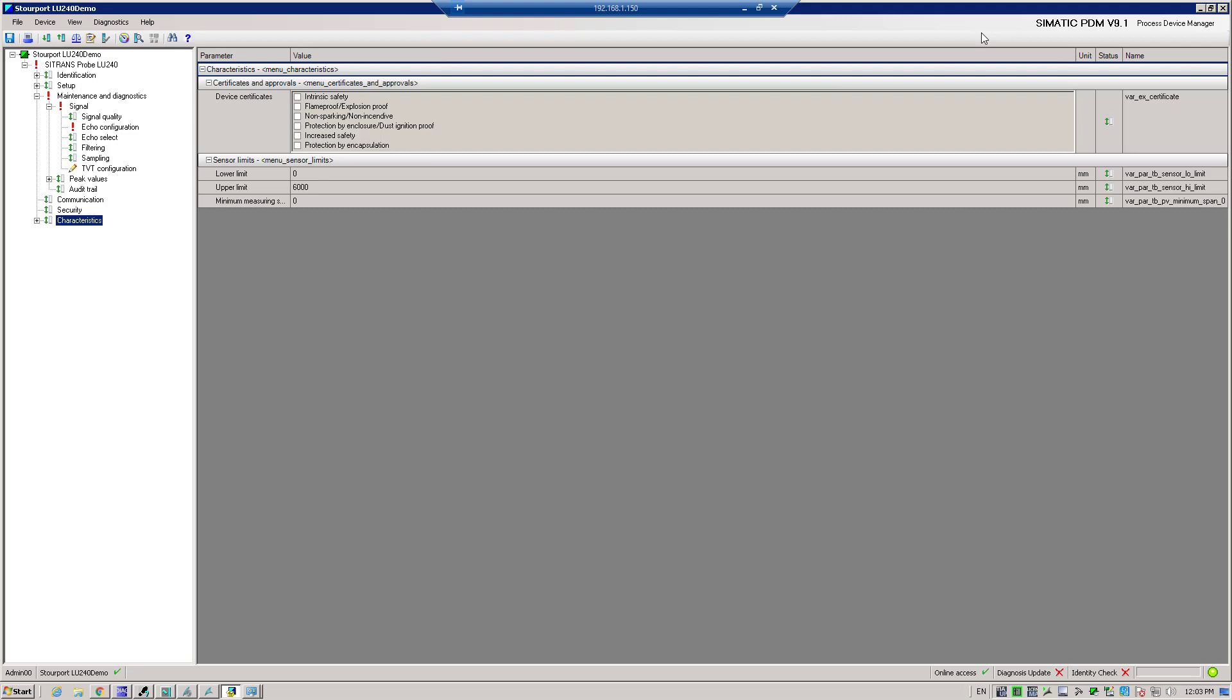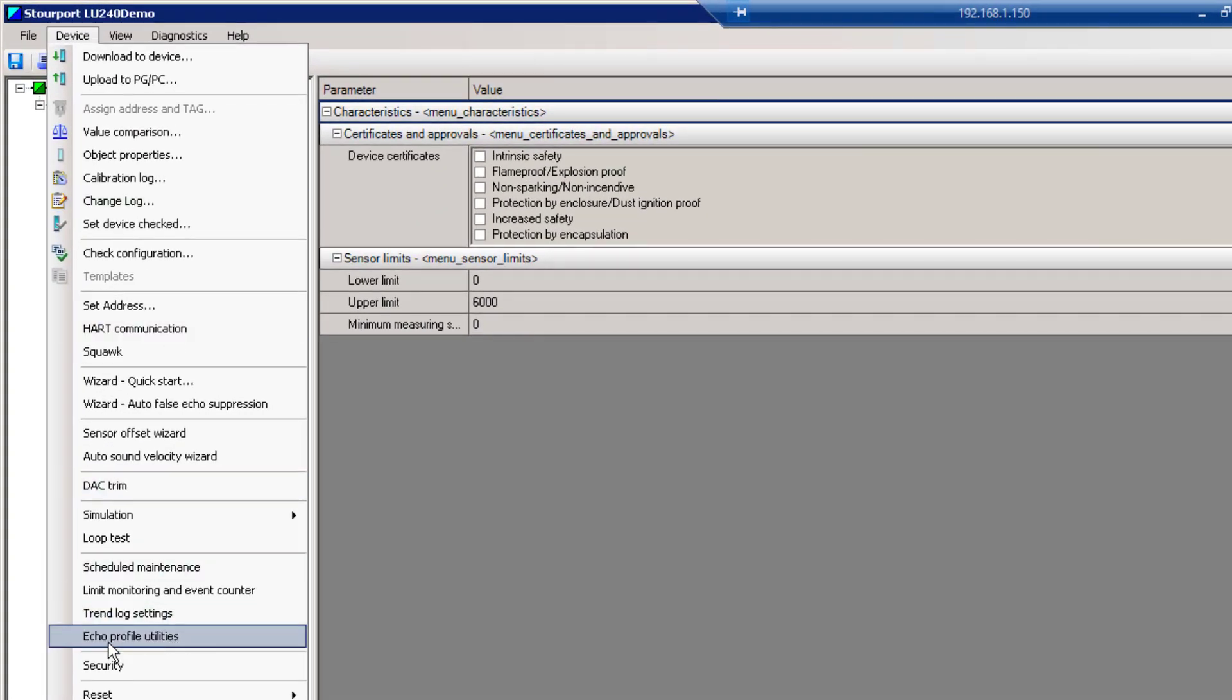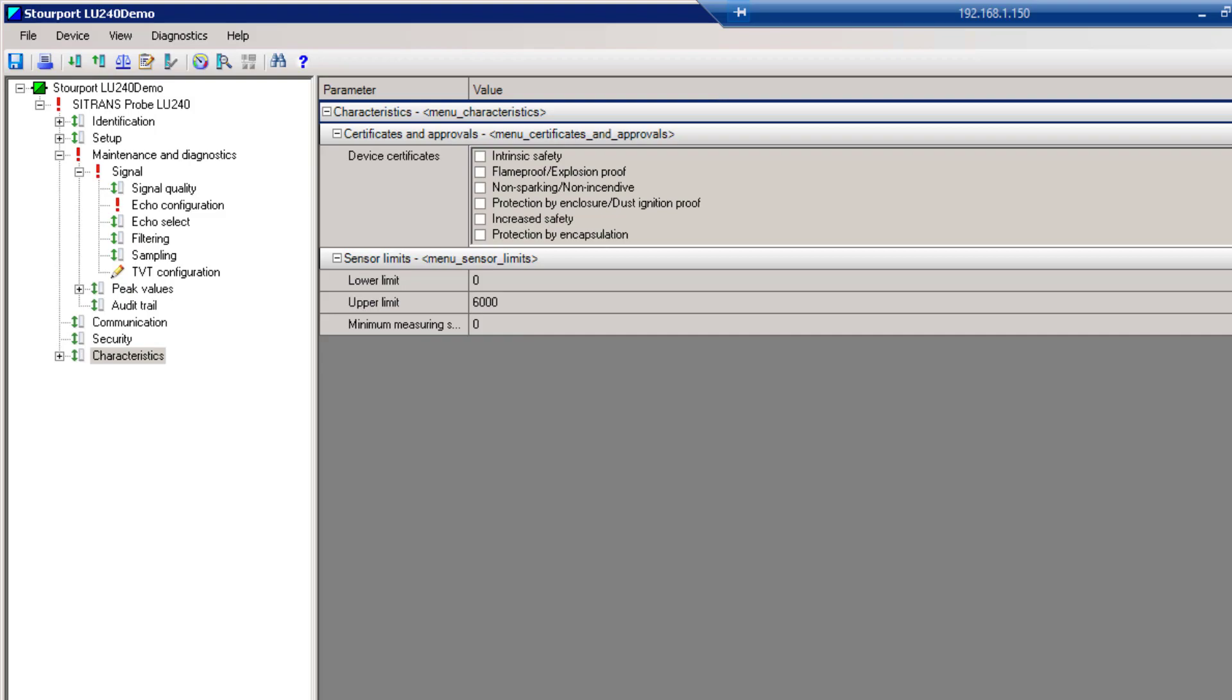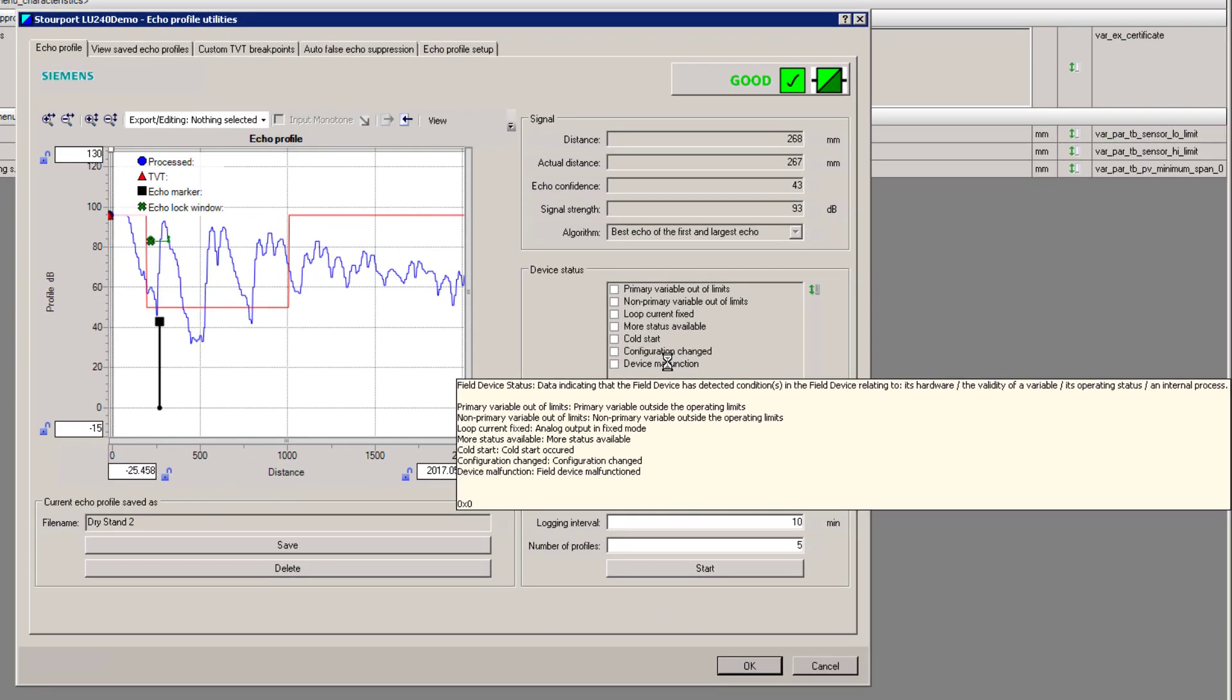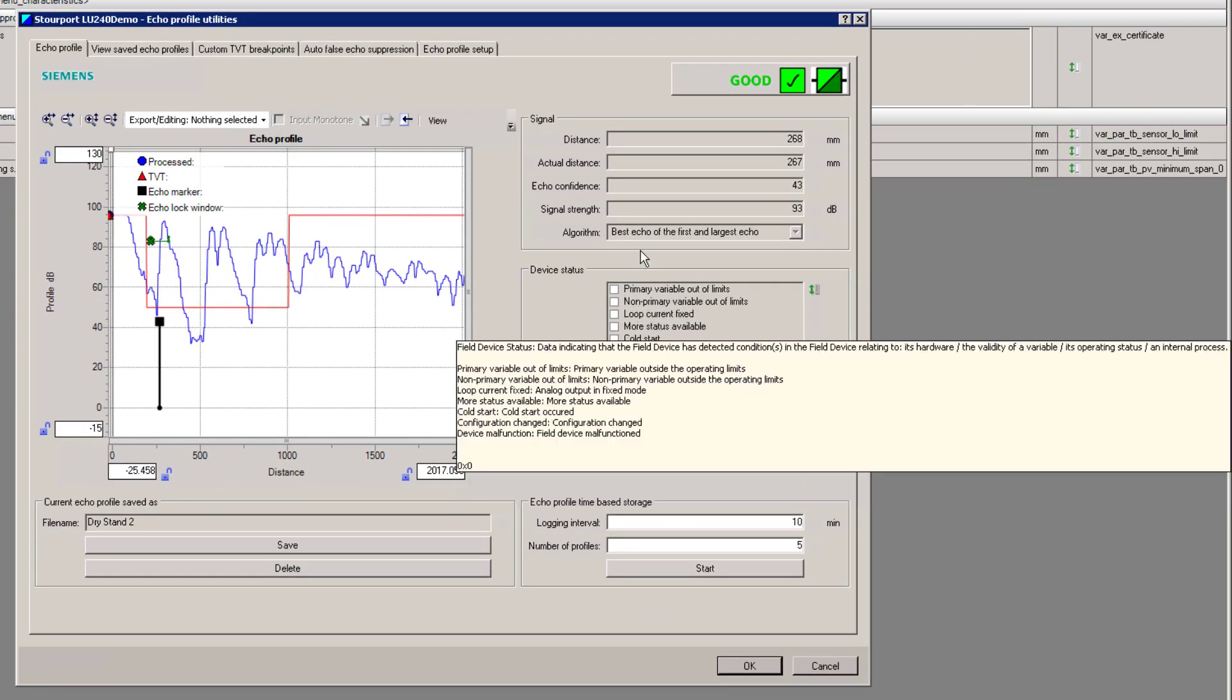We're going to get the transducer face wet by spraying on condensation or simulating condensation, and we're going to actually look at the echo profiles to see what happens to the signal strength. Here we have PDM open. To look at the echo profiles it's under the device menu, and this is pretty much the standard for all Siemens level devices. We have something here called echo profile utilities. The values we're going to be looking at are distance, echo confidence, and echo strength. To get an echo profile we click on measure.